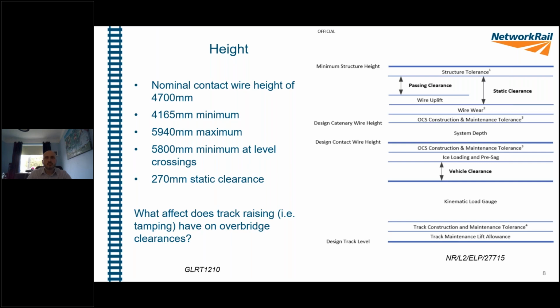This is because High Speed 1 was purpose-built for electrification. Therefore, any bridges over the railway line are high enough to have the clearances required, and there are no level crossings on the route. At level crossings, we've got a minimum wire height requirement of 5.8 metres, and this is to ensure vehicles can pass safely underneath.